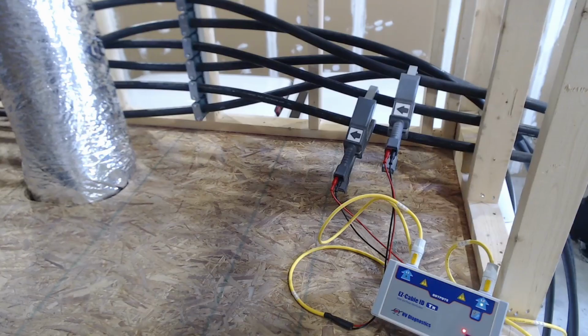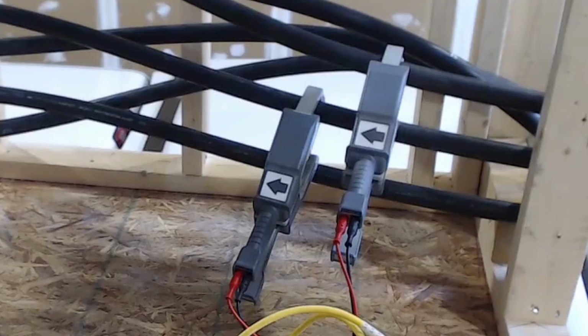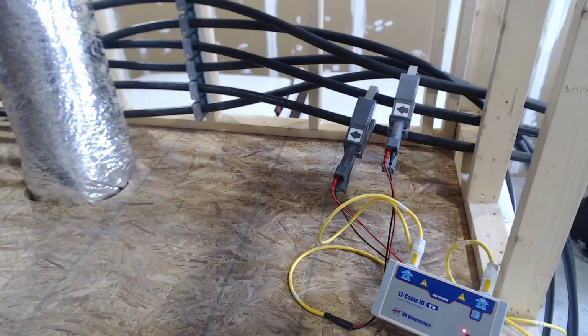Now we are going to demonstrate the indirect mode with the CT clamps. Notice the direction the arrows are pointing. That indicates the direction the pulse is going to be induced into the shield. With that being said, only one or two phases can be identified this way, as compared to the direct mode, where you can identify all three phases at a time. Note, indirect mode can only be done between grounding points on the neutrals of the cable.